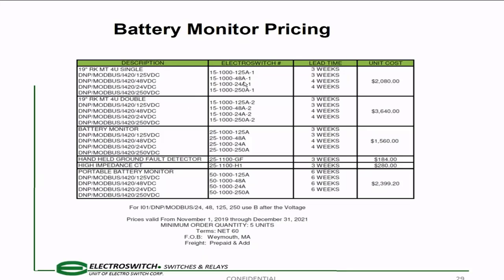All right, so we have 24 volt, 125 volt, and 48 volt DC systems, okay? And actually, this identifies all the leads. So when you're looking at this, the 19-inch rack mounted is 4U, okay? So it's all 1000, but it's designated by 15. Okay, 15 is the rack mounted 4U system. So you can see 15-1000-125A-1, 48A-1, 24A-1, 250A-1. So these are all the ones with DNP, Modbus, 4-20, okay? And it's 3 weeks. When you go to 24A-1, 250A-1, those are not the typical ones that people would order, so the lead time goes out to 4 weeks, okay? Most of the time, you're going to come across the 48 and 125 volt DC systems.